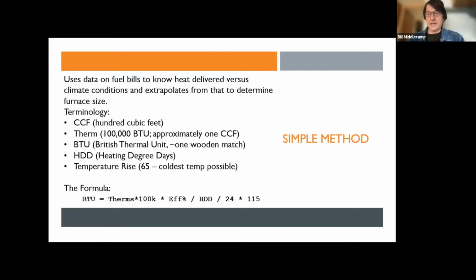My method simply uses the data that's provided on fuel bills from CenterPoint, and that tells you how much heat was actually delivered under certain climate conditions. And this method extrapolates from that to determine what furnace size you actually need.